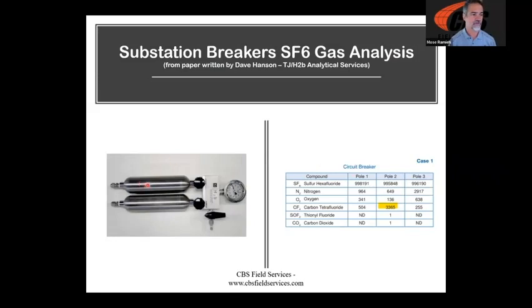We have one cylinder that comes in completely evacuated. One bottle is used to take a waste sample, so basically the air in the line is purged. And then the second bottle is used for the actual quality sample. And then we close off the system, and it's a very thin little tube, almost the size of a human hair. So when we break those connections loose from the gear, we are losing the minimal amount of gas possible, as opposed to some of your standard test sets that only test moisture and quality.